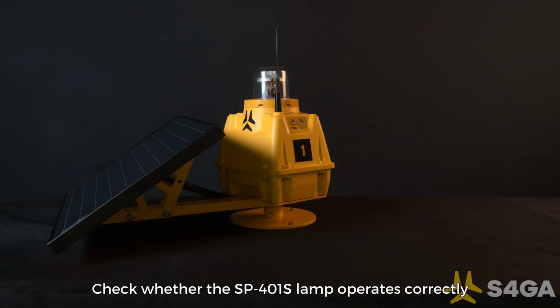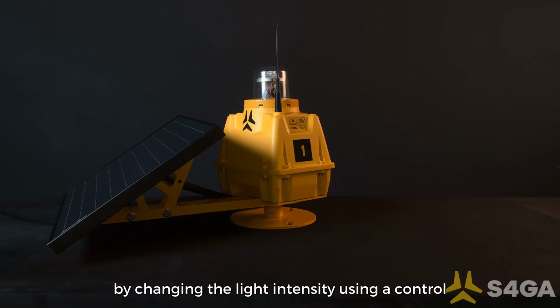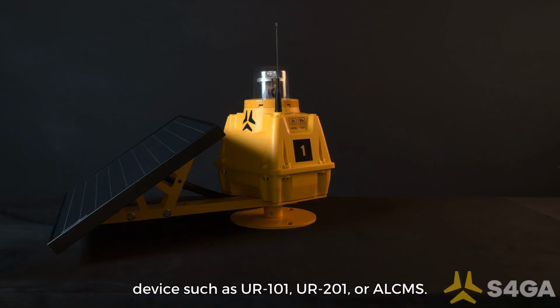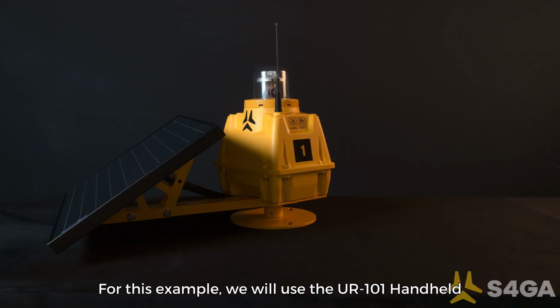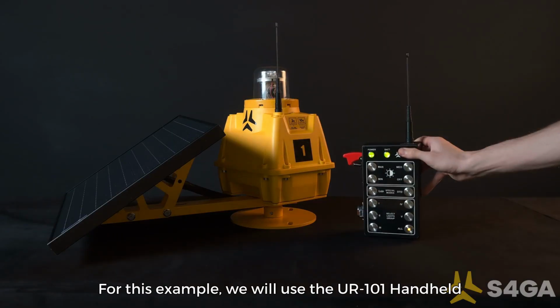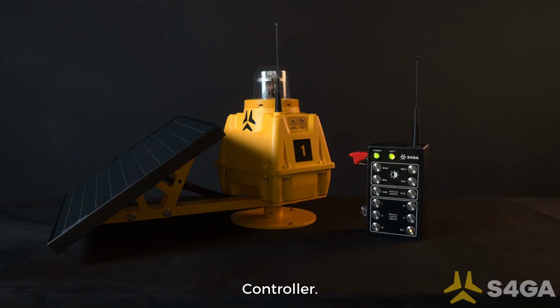Check whether the SP-401S lamp operates correctly by changing the light intensity using a control device such as UR101, UR201, or ALCMS. For this example, we will use the UR101 handheld controller.